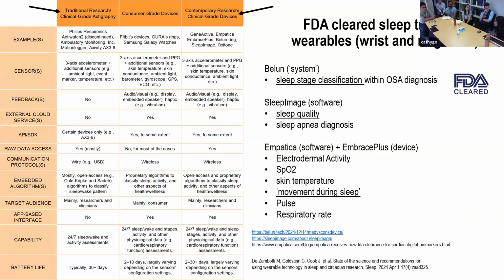It has a piezoelectric accelerometer. That's a solid state accelerometer, not just that MEMS microchip. It measures motion triaxially. It gets plugged back in, downloaded to a software package, and then it's essentially a weighted sum that's looking at each 1 minute increment of data. And if the sum is above 40, it's going to score it as wake. If it's below, it's going to score it as sleep, at least on the medium threshold. And that's how you get those actigrams with the Respironics actigraph. But again, those are discontinued.